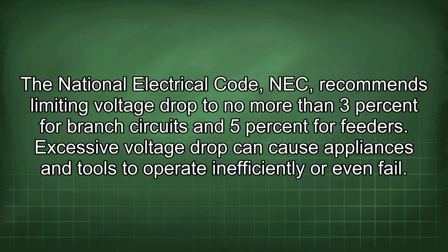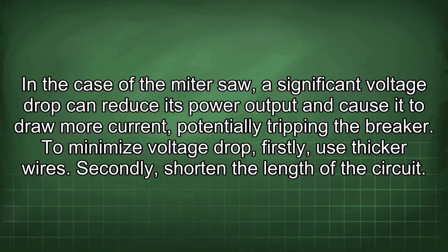The National Electrical Code, NEC, recommends limiting voltage drop to no more than 3% for branch circuits and 5% for feeders. Excessive voltage drop can cause appliances and tools to operate inefficiently or even fail. In the case of the miter saw, a significant voltage drop can reduce its power output and cause it to draw more current, potentially tripping the breaker.